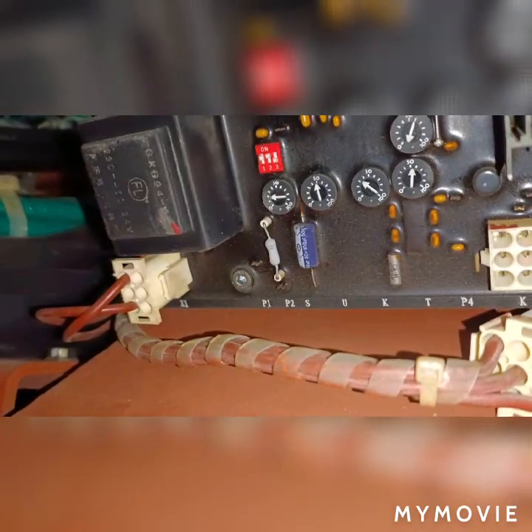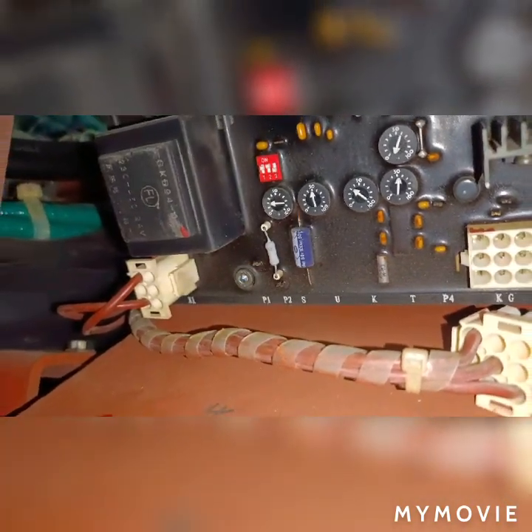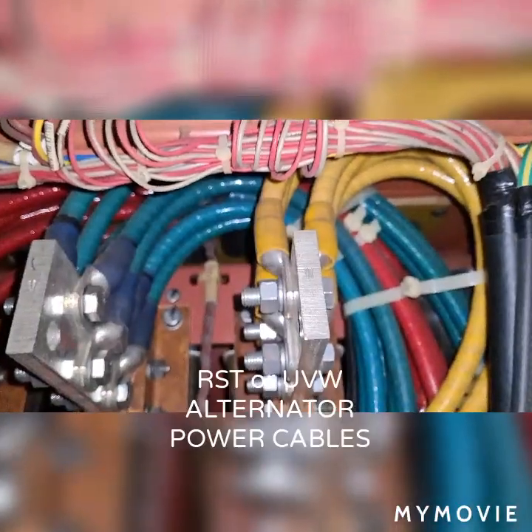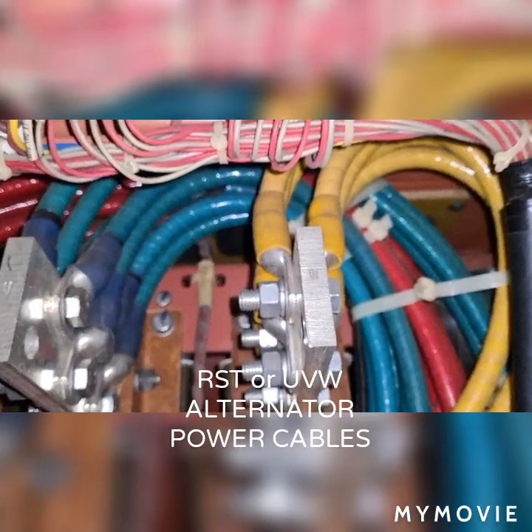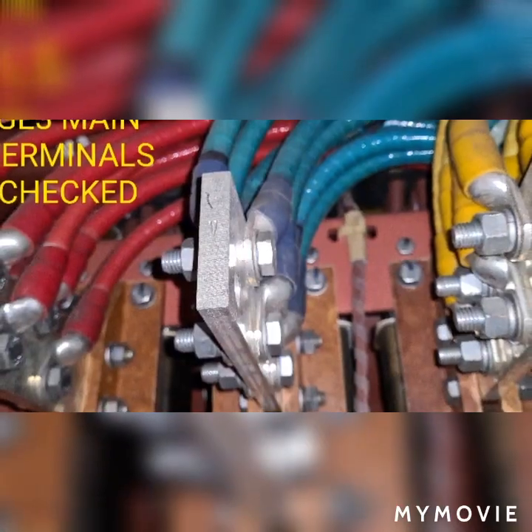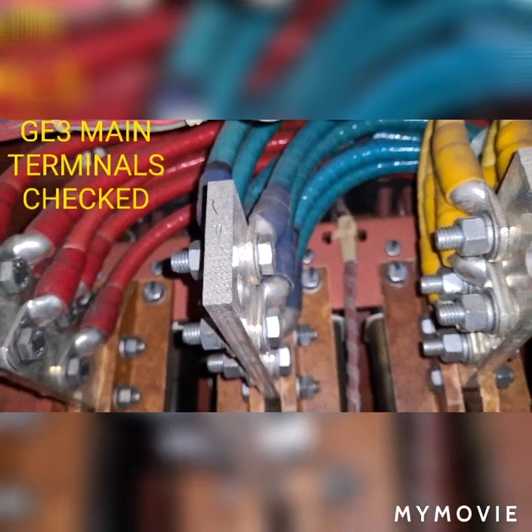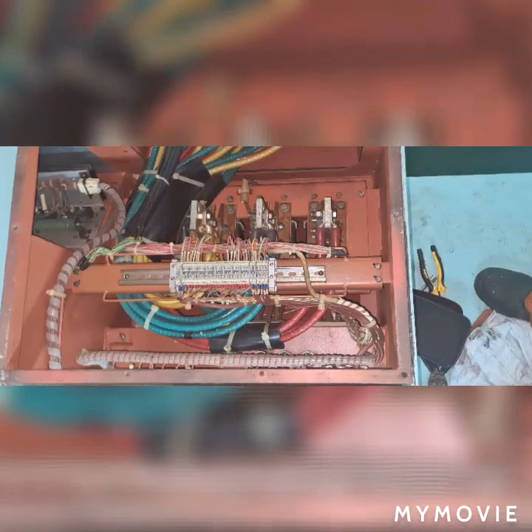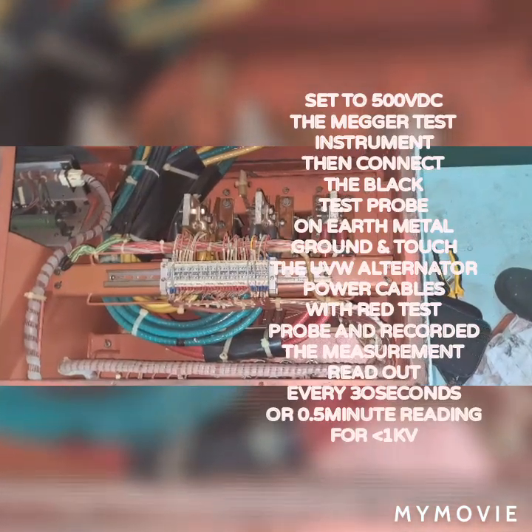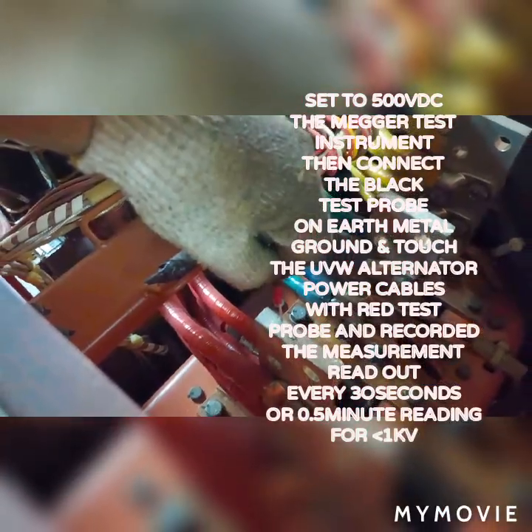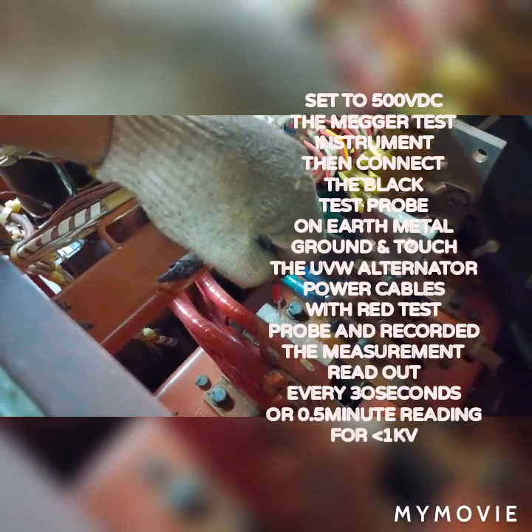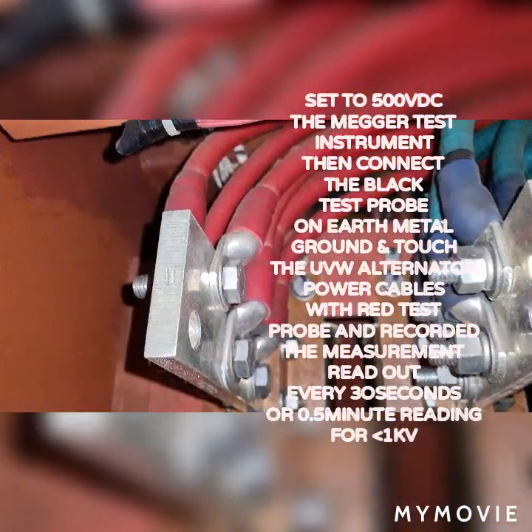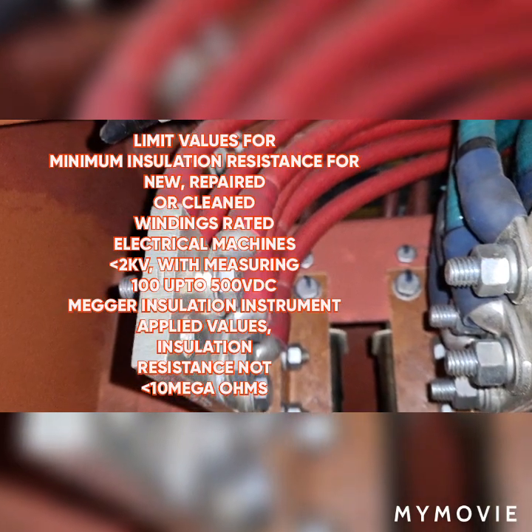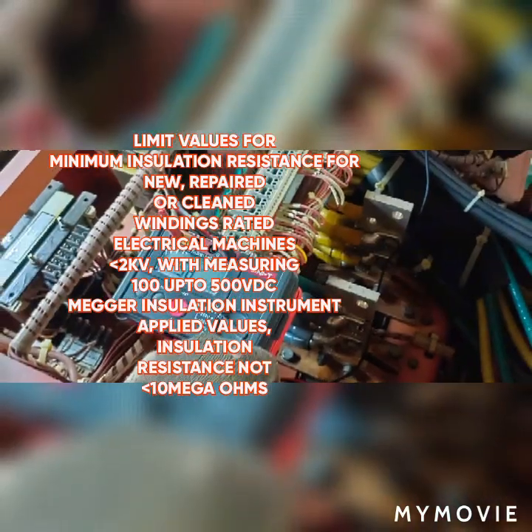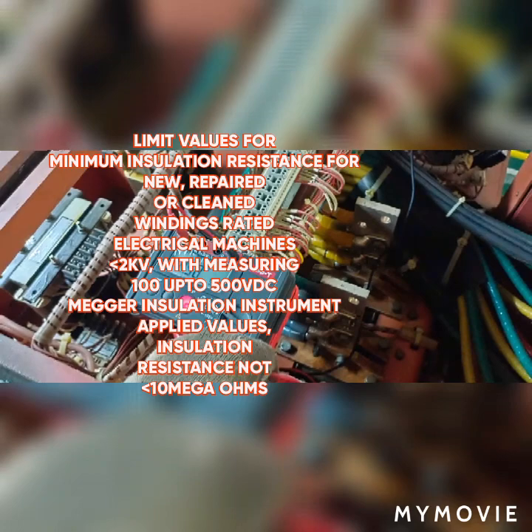Okay guys, since we already isolated the AVR plug connectors X1, X2, X3, X4, the fuse on the power generators on the main switchboard, and isolated the circuit breaker, we are now going to proceed with the Megger insulation check. Take note, in doing a Megger insulation check, we must consider the rated voltage of your electrical machine.